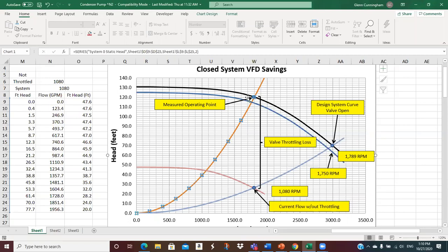Okay, so the idea here is let's open the valves and come out and operate on this curve, and then let's slow this puppy down until we operate right here. And my goodness, this is far less energy. Look at the savings in head. You know, what is that? That's about 27, 28 feet versus 120 feet. I mean, that's just outrageous.